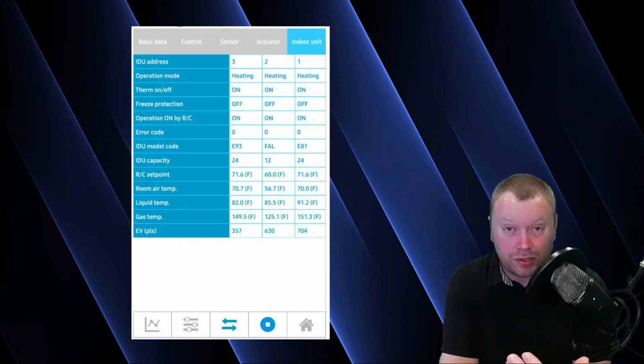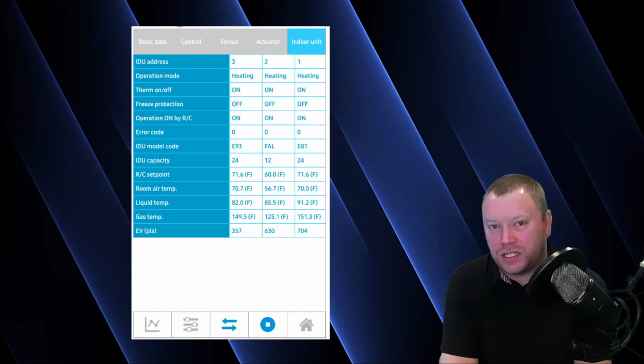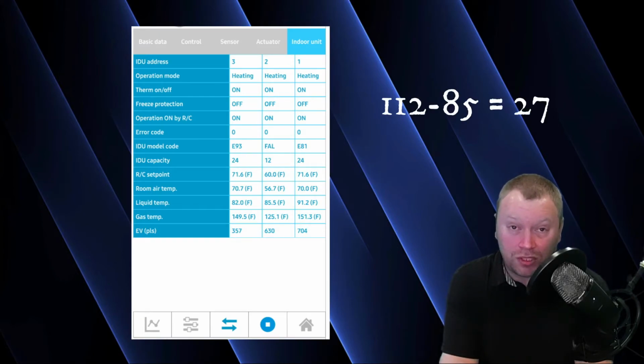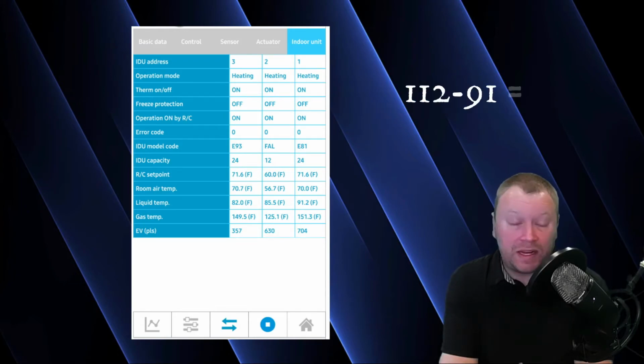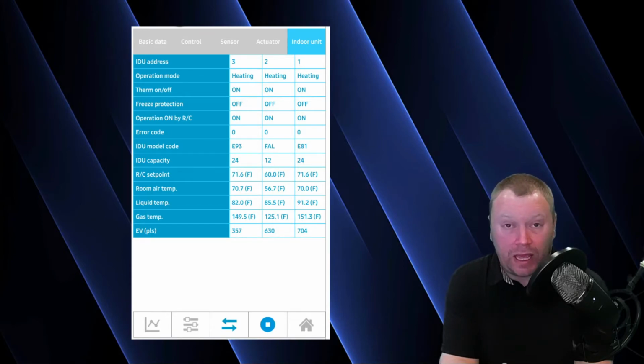And then, of course, as you get closer and closer to the set point, regardless of the amount of subcooling you have, that EEV is going to throttle down because we don't want to overshoot our set points. So as we're running our calculations, you see unit 3 has a near 30-degree subcooling, which is at the high end of our range. If you look at unit number 2, it is also high. Unit number 1, 91-degree liquid temperatures. It's still high, but it's closer to 20, which isn't as bad.